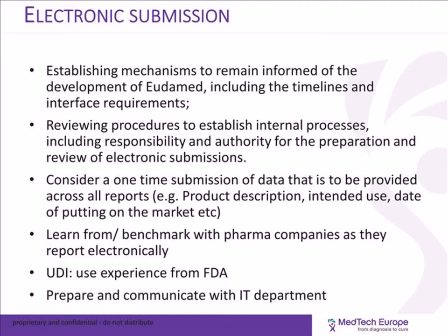A manual submission to EUDAMED, especially if you have a large portfolio of products, will rapidly become unmanageable. And there is a need that all this procedure is automated and the feeds are really created into the electronic submission.